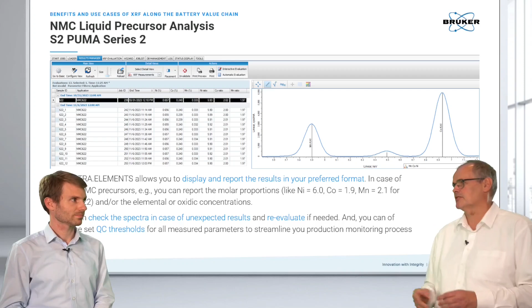And last but not least, for this liquid precursor use case, just a precision test here. What we've done is we remeasured the sample 12 times. We prepared it each time, we loaded it each time, so really like in the real world, not measuring the same sample every time. And you can really see that we have an extraordinary stability here. We produce a relative standard deviation of around 0.1% for nickel, manganese, and cobalt. And we can then, of course, determine relatively easily what our thresholds are and meet them, and that in just 2 minutes. So actually the relative standard deviation is excellent here and enables a very close monitoring of the production process. That's it. Exactly.